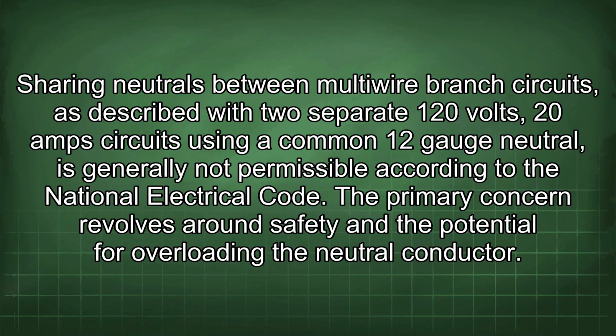Sharing neutrals between multiwire branch circuits, as described with two separate 120 volt, 20 amp circuits using a common 12-gauge neutral, is generally not permissible according to the National Electrical Code. The primary concern revolves around safety and the potential for overloading the neutral conductor.